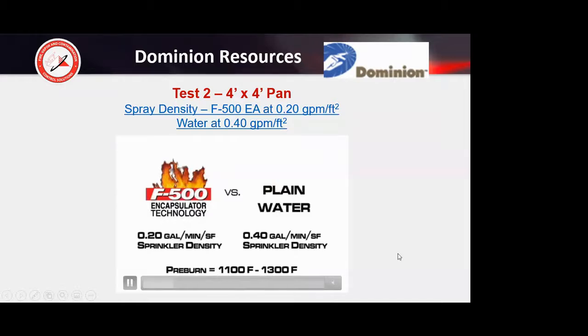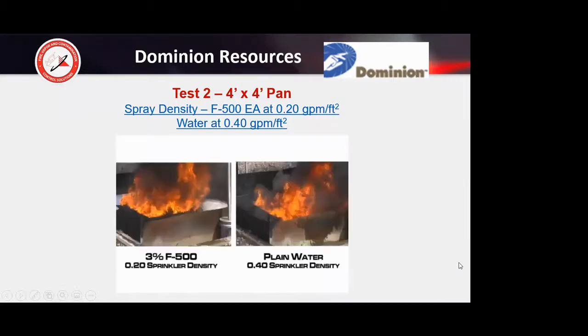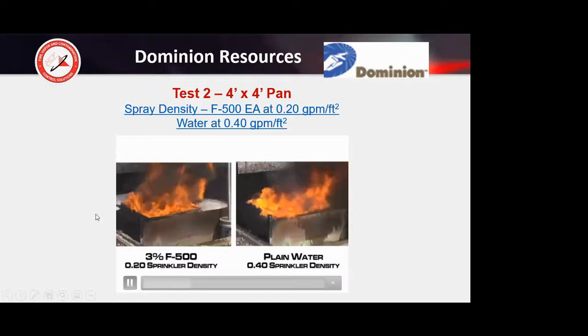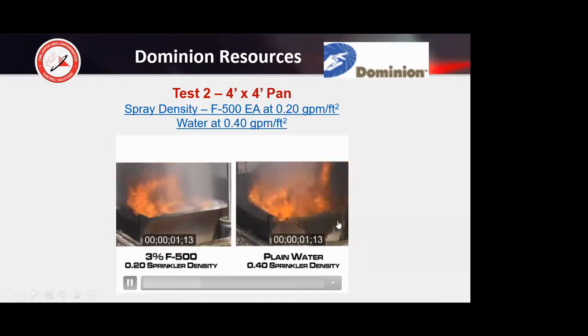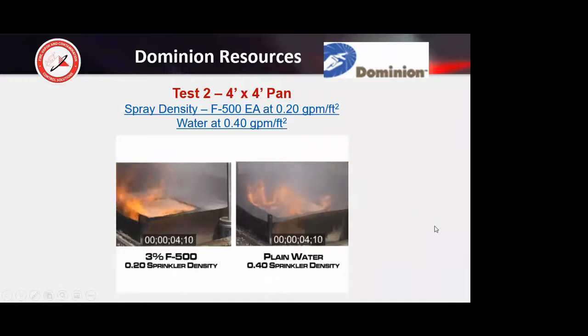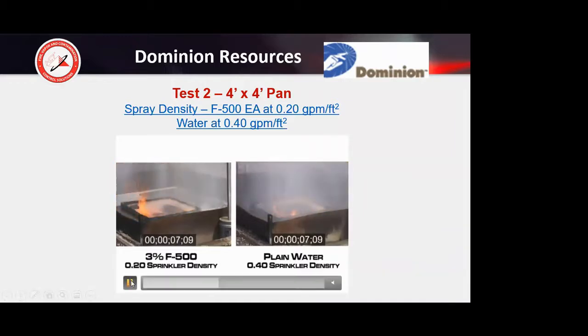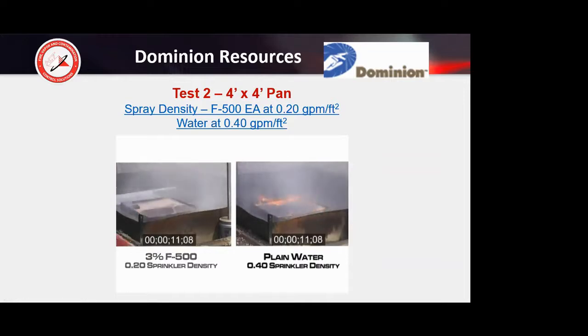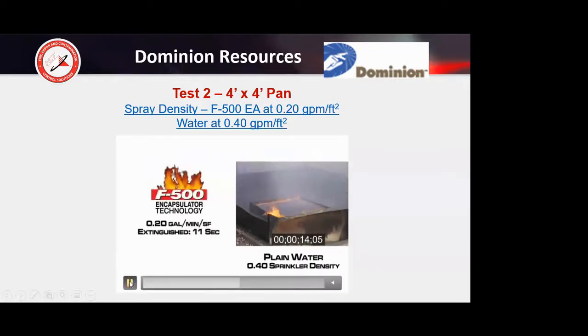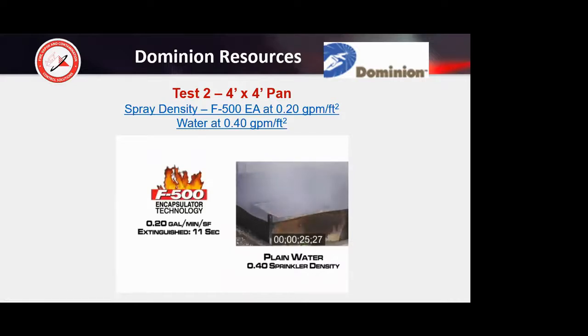Again, pre-burn up to 1100 to 1300 degrees. You've already seen this. This is 11 seconds, but we're putting it side by side with the water. Here you see it looks like they got pretty good knockdown, almost the same, even though this is half the amount of water, almost the same. But again, we see the issue here is the fire continues to burn around the side of the pan because you can't reduce the heat. You're using a very ineffective steam conversion to reduce the heat.